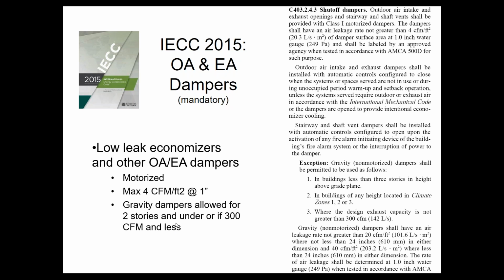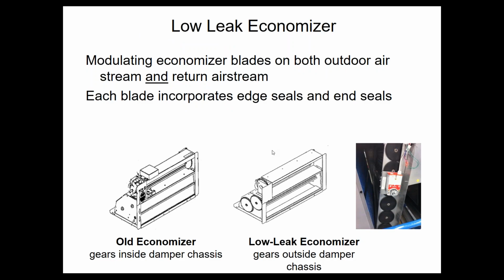Once you have a motorized damper, either because this section of the code requires it or because the economizer happens to be motorized anyway, as soon as you have a motorized damper, it must be low leak. And it tells you up there in the first paragraph, it's got to meet AMCA 500D certification for low leakage. What that means to you guys visually in the field is that the damper blades will have seals on the edges and on the ends, which is kind of expected, but also the gears for the economizer will no longer be in the airstream, they'll be on the outside of the airstream.